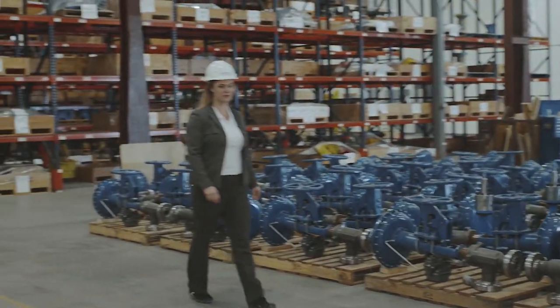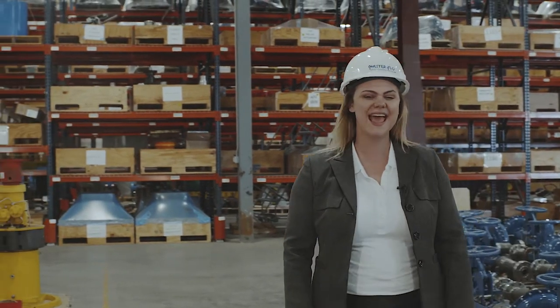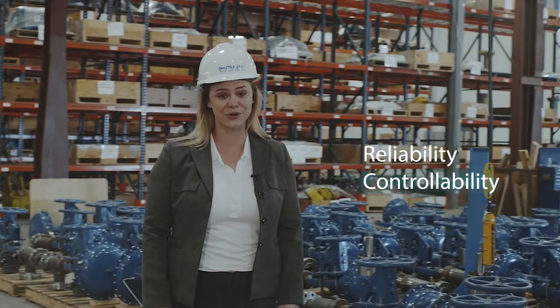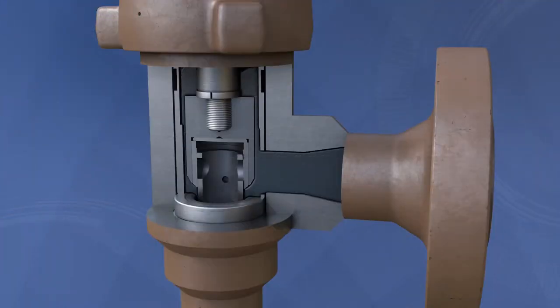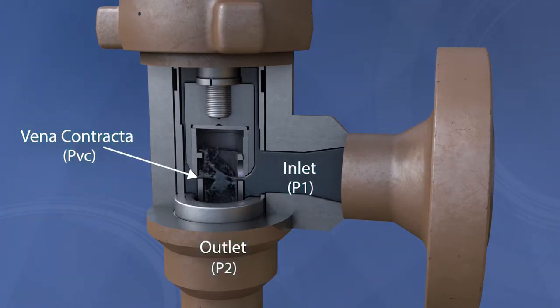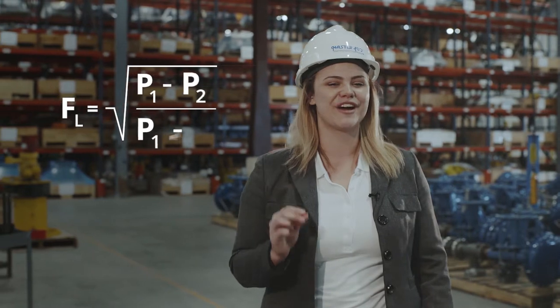Custom trims allow elimination of the need for parallel valve operation, thereby reducing maintenance while increasing reliability and controllability. In production, only inlet and outlet pressure values are measured. However, inside the valve at the throttling point, the pressure is much lower. This is designated as the vena contracta pressure — an important factor of the choke valve selection process, along with liquid pressure recovery.